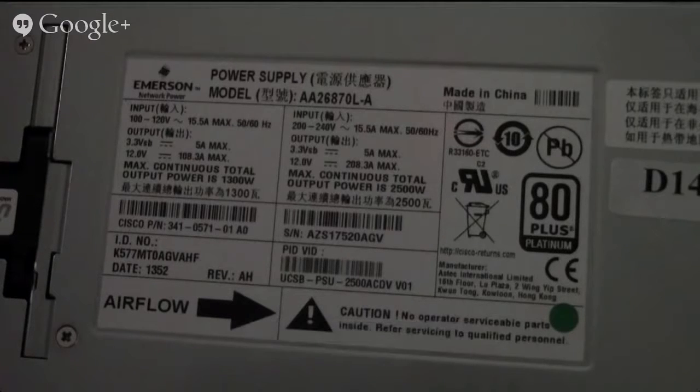So we might get to a point, depending on blade configuration, after maybe 4 to 6 blades, where the 7th blade wouldn't be allowed to be powered up because we wouldn't have enough power to power that blade and keep redundancy. So that's something that we definitely had to do a lot of work on, and people need to be aware that when you run at low line voltages, you could run into some limitations on the number of blades that will actually power up.